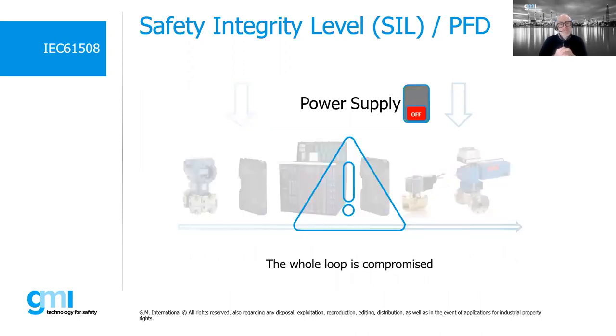Let's ask ourselves now, why shouldn't the power supply system that feeds the whole system be SIL certified? Why shouldn't we make sure that the system that supports the entire SIF is also certified for functional safety? Keep in mind that the failure of the power supply system can cause the complete loss of our loop, with consequent losses in terms of productivity and therefore of money. It's also really important to make the power supply system that supports our entire safety loop safe and reliable.